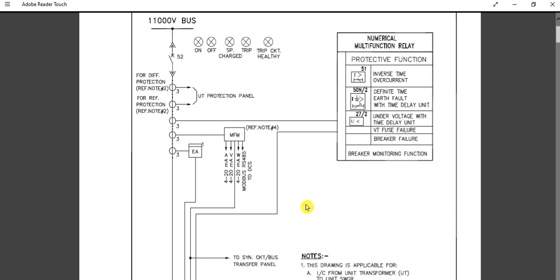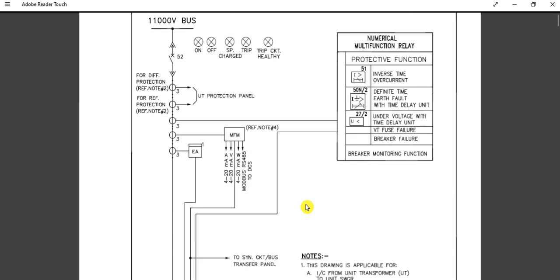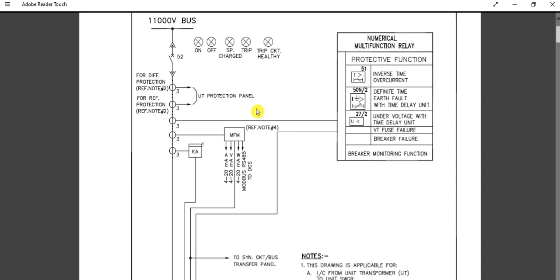Differential protection and restricted earth fault protection are not provided for small rating feeders — they are required for higher-rated transformer incoming feeders. In this lesson we have learned the typical metering and protection diagram for 11kV or 6.6kV medium voltage switchgear.